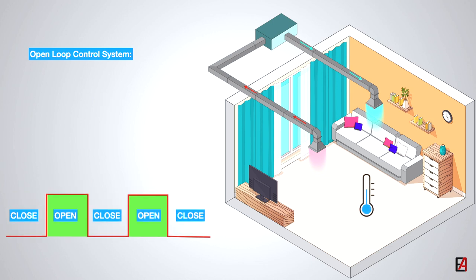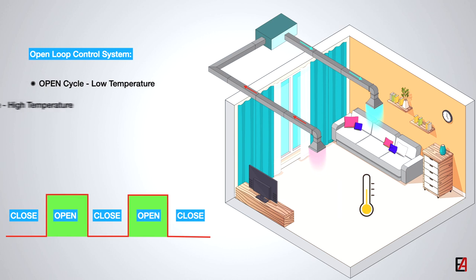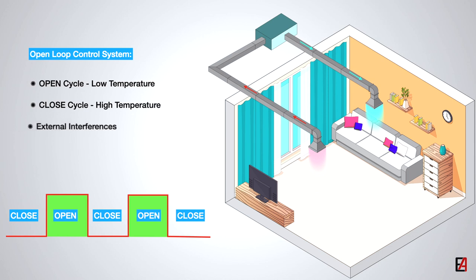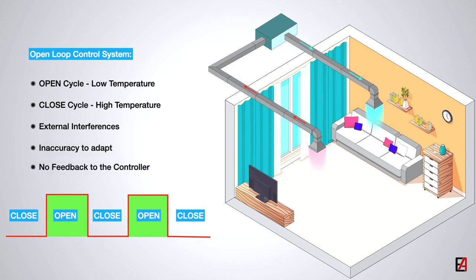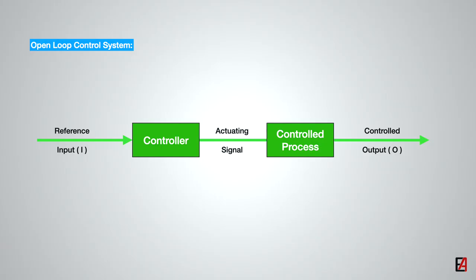During the control valve open cycle, the room temperature will be below the desired temperature, and during the control valve close cycle, the room temperature will be above the desired temperature. As it is impossible to calculate the amount of time required to keep the control valve open or closed to achieve the desired temperature due to external interferences such as outside temperature, varying chilled water temperature, etc., it is clear that the desired room temperature cannot be achieved with this type of control system due to inaccuracy in adapting to external interferences and unavailability of any feedback signal to compare with the desired space temperature.